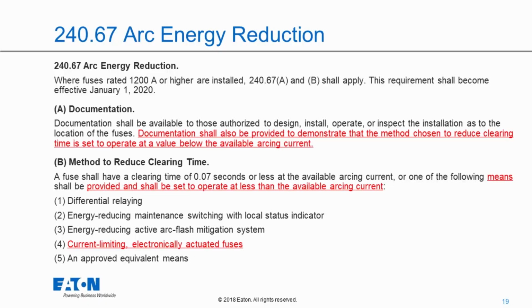So since the 2017 NEC, we've had to document the location of the fuses, okay? In the 2020 code, we added additional requirements to document that the method chosen to reduce the clearing time is set to operate at a value below the available arcing current. And for those of you who perhaps are not familiar with arc flash studies, you're probably very familiar with how to determine the available fault current, but perhaps you're not as up to speed, if you will, on how to calculate the available arcing current. And I'm going to give you some tools on how to do that in my next couple slides.